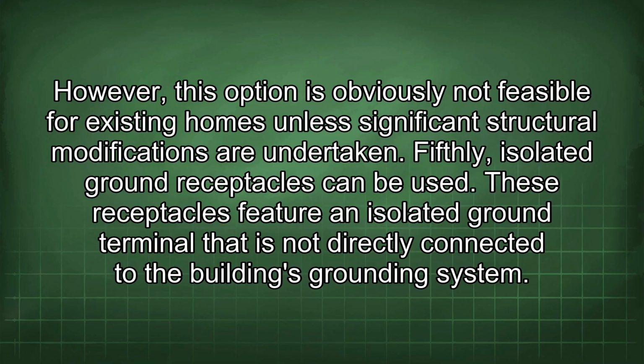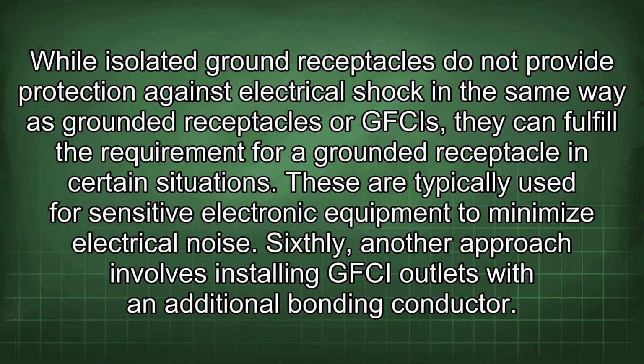Fifthly, isolated ground receptacles can be used. These receptacles feature an isolated ground terminal that is not directly connected to the building's grounding system. While isolated ground receptacles do not provide protection against electrical shock in the same way as grounded receptacles or GFCIs, they can fulfill the requirement for a grounded receptacle in certain situations. These are typically used for sensitive electronic equipment to minimize electrical noise.